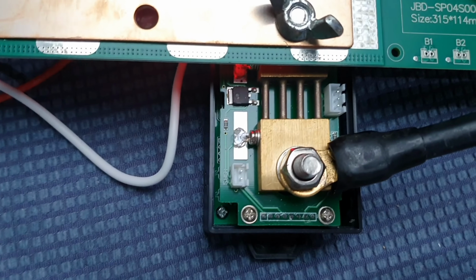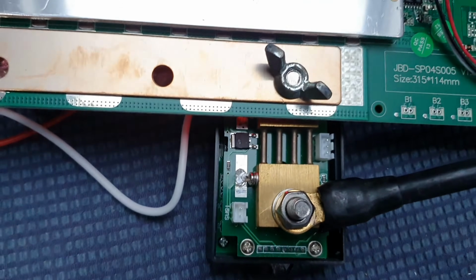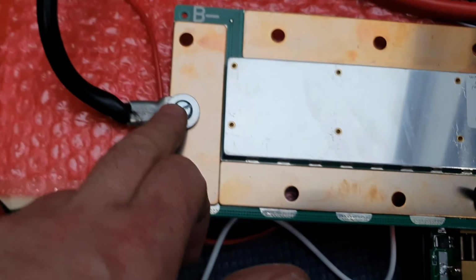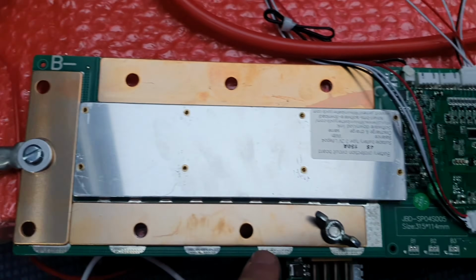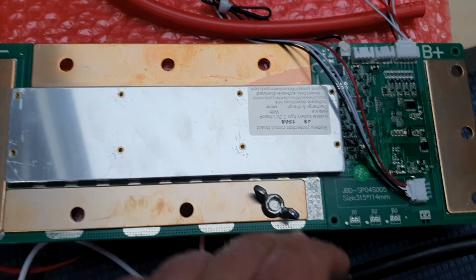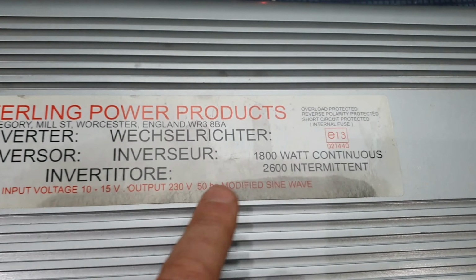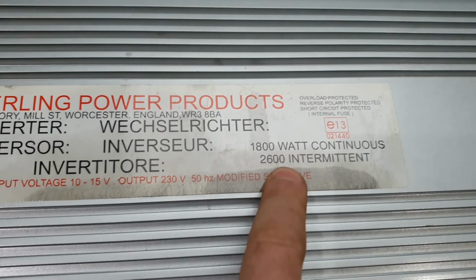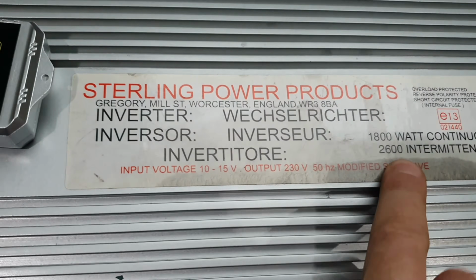There's then a shunt, a 300 amp shunt wired into this. The negative off the battery comes into B minus, then off the BMS into the shunt, and then the shunt negative to the inverter, which is a Sterling 1800 watt continuous, 2600 watt intermittent or burst.